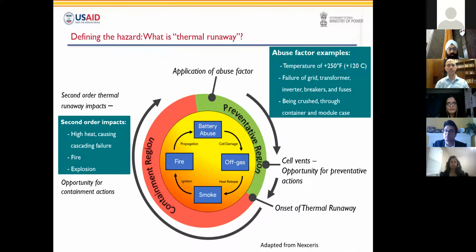These abuse conditions may be thermal, for example, high temperatures in excess of 250 Fahrenheit, which is 120 degrees Celsius. Electrical shorts and failures, or mechanical: crushing, pressure, shooting, a truck driving into the battery, someone shooting at the battery, etc. Under an abuse condition, a battery system will generally emit off gases, and these can be detected for mitigation. Preventative actions can be taken to remove the abuse condition from the battery before the battery goes into thermal runaway. For example, one of these is venting. The tops of most lithium cells pop off for pressure release and venting, and this removes the abuse condition. Another example of preventative measure is tripping off electrical components.